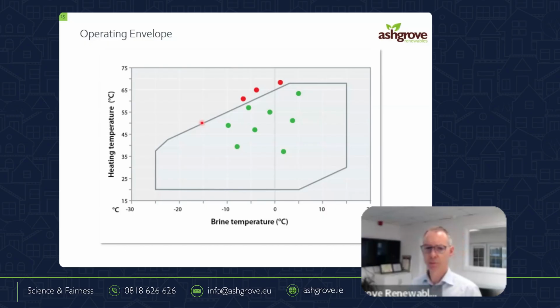Even though the heat pump box says it can reach whatever, 67 degrees. But if I'm cooling at a certain temperature, it limits me on the other side. If I need more than that, but I do need the minus 15, well, that's the end of it. This heat pump can't do it. Yeah. It's moved to a different gas then, or a heat pump that has a different gas. So it's the wrong heat pump for that particular application. 100%. Yeah.